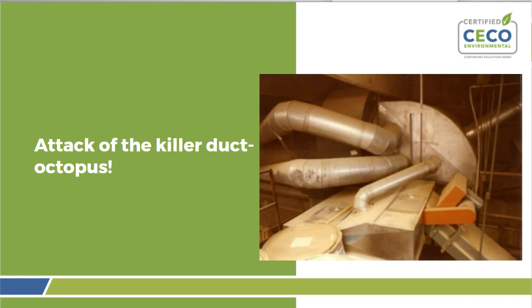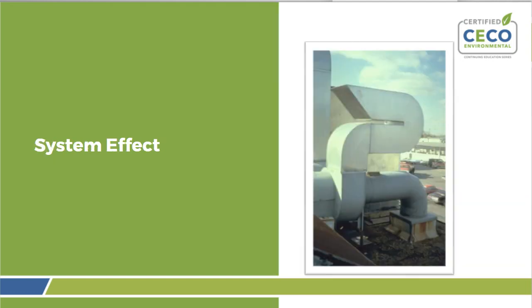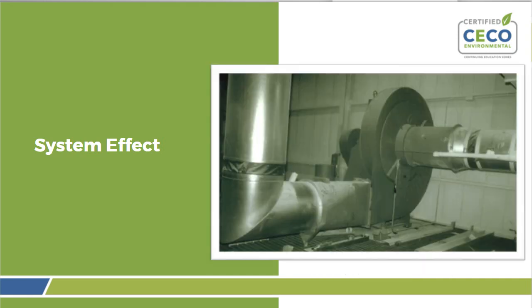System effects, another slide of shame. Anything that you do at the fan inlet or outlet that's not per how you should do it, you're going to have effects. In this case, they're breaking the airflow. It's spinning. It's turning it 90 degrees from the way it should have spun, and then they decided to add this 180-degree elbow, blowing it back the other direction. This is another system effect, having an elbow too close to the fan outlet. In this case, it's a two-piece elbow, so you have loss from the elbow being too close and not having a proper elbow.